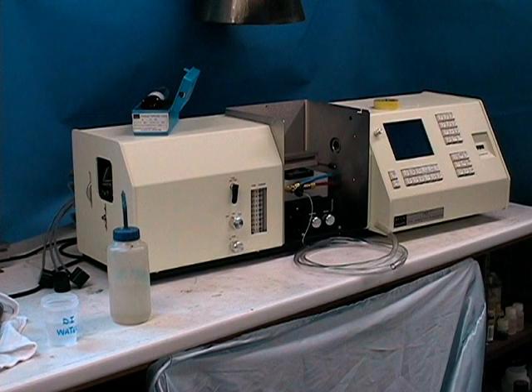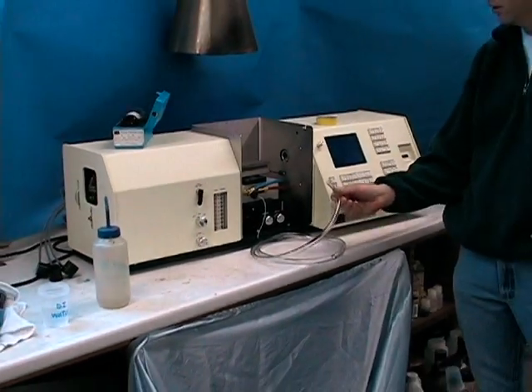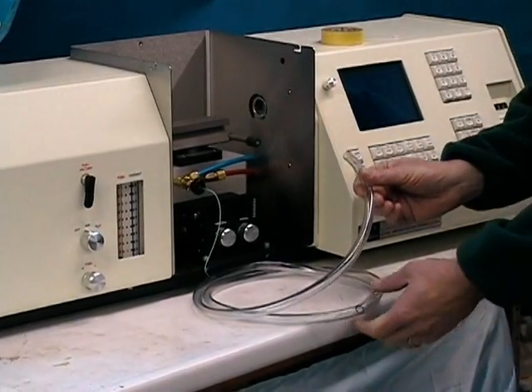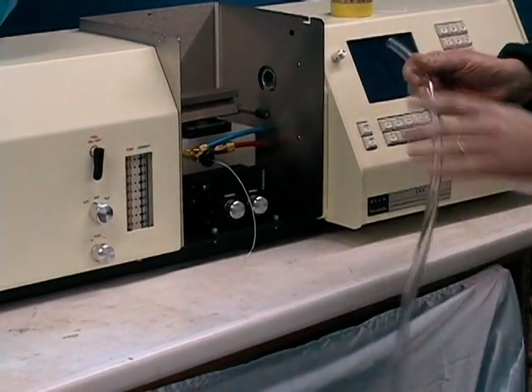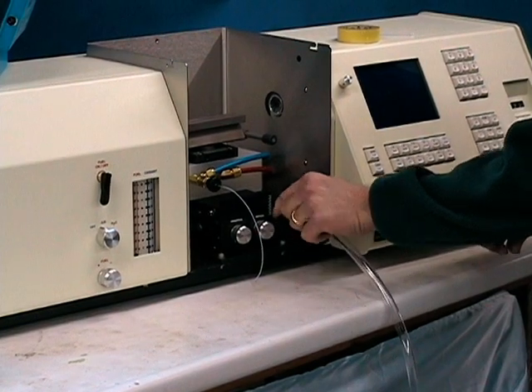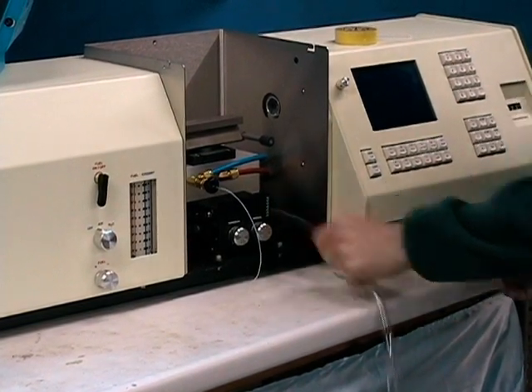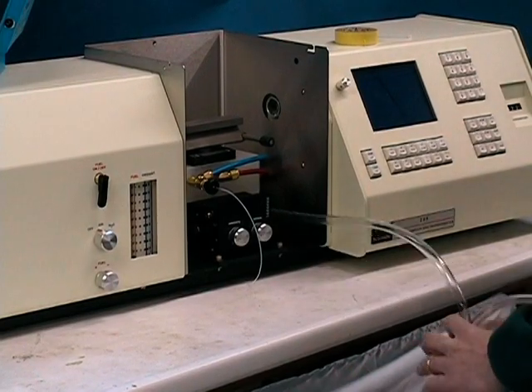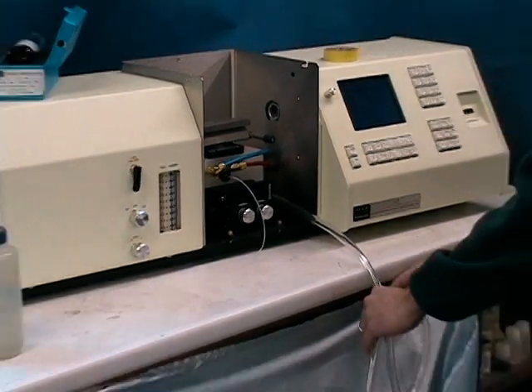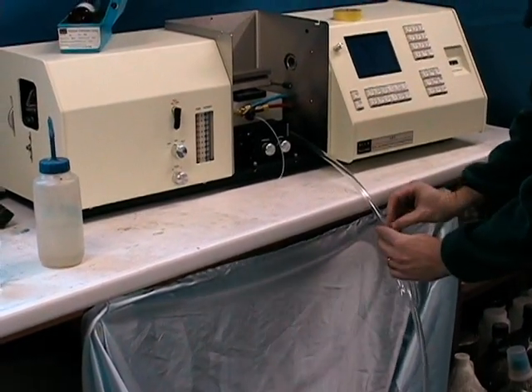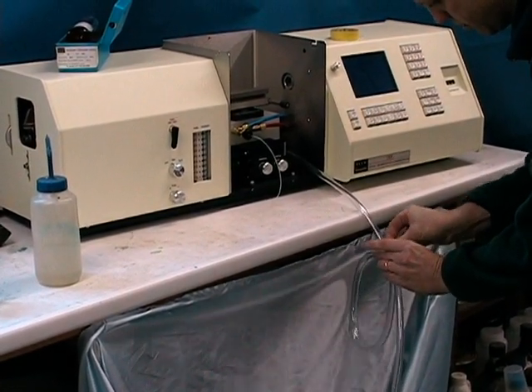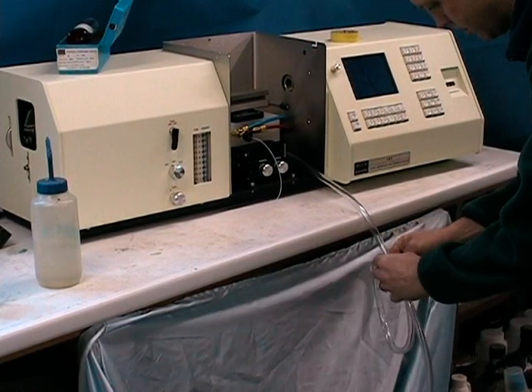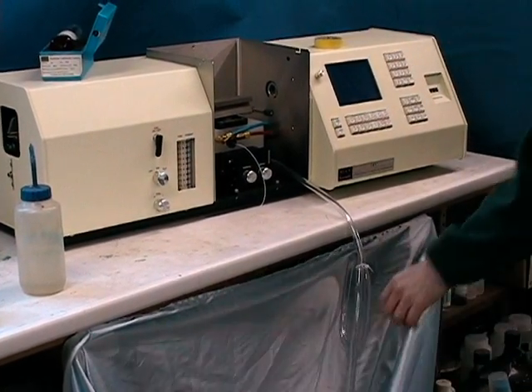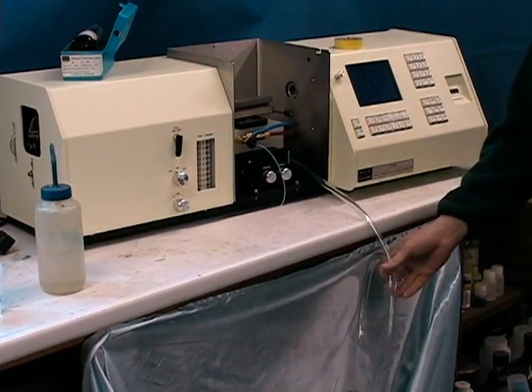Prior to doing an analysis, there are several other connections that need to be made on the front of the instrument. The most important of these is the drain line. Included with your installation kit is a piece of soft Tygon tubing. This is inserted onto the black nipple on the right side of the burner head. And after you position the instrument no more than 3 or 4 inches from the front of your counter, you want to prepare a loop to act as a vapor trap, and then using the included cable tie or a piece of duct tape or electrical tape, attach a loop to the system about 4 to 6 inches in diameter.